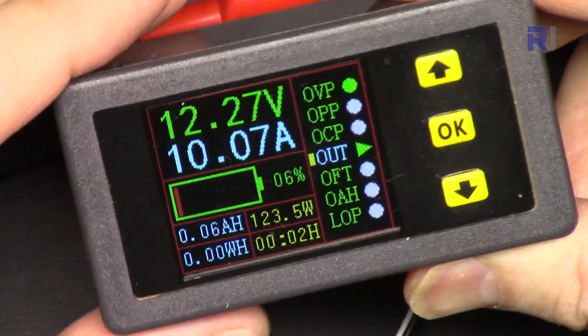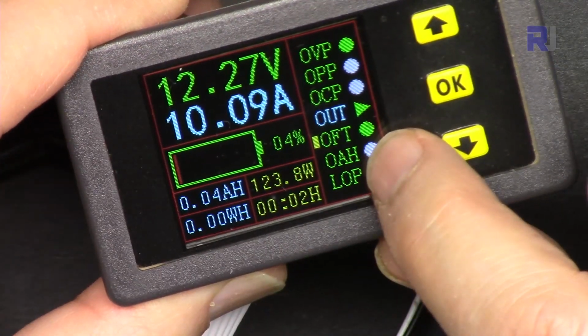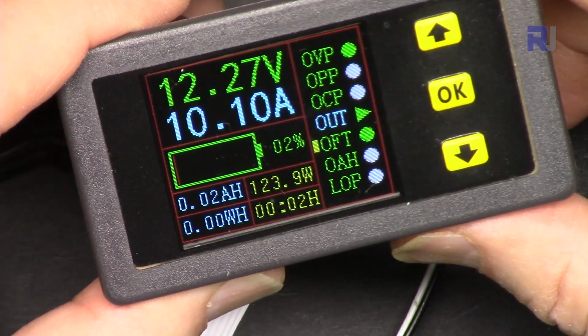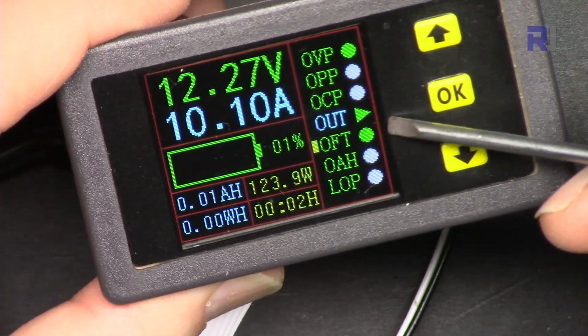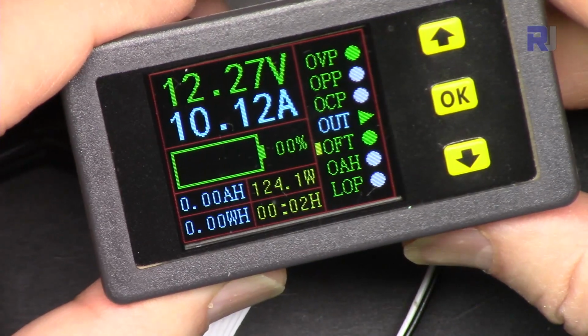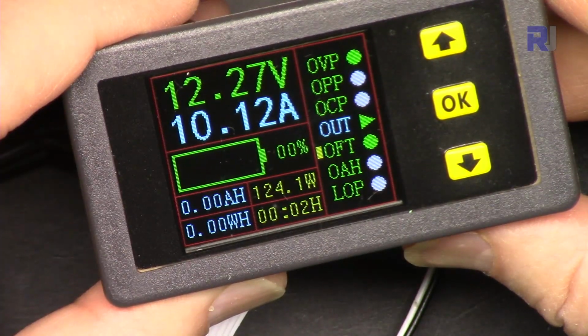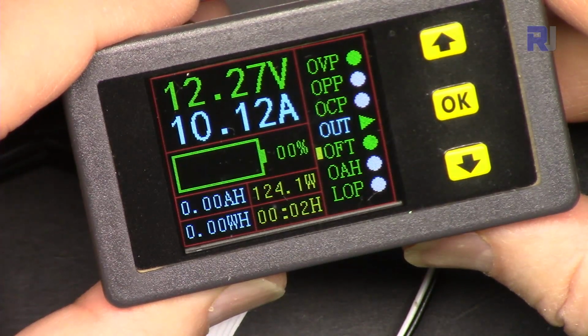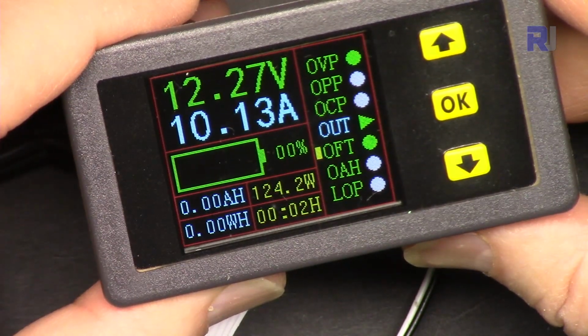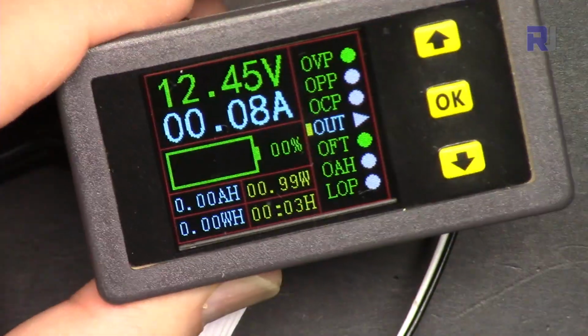I set the current to 10 ampere. Do not worry. So let's turn this on. Now it's on. What does it do? It will start from now. So it just blinked. But still we have current, so we have to see that this will turn off. So 2 minutes passed and it was disconnected.